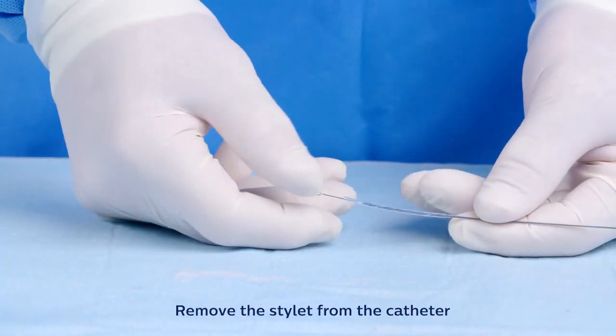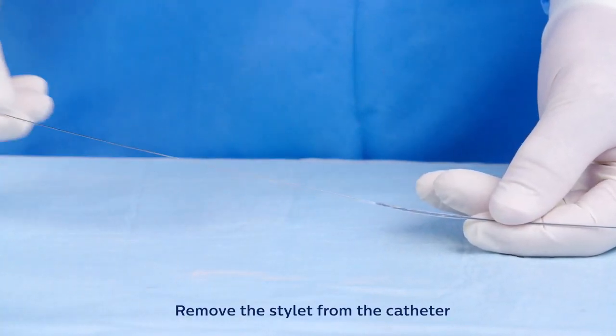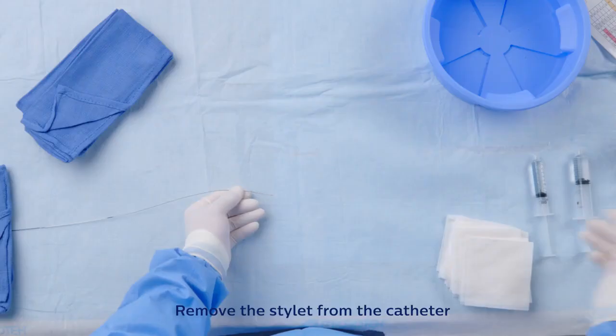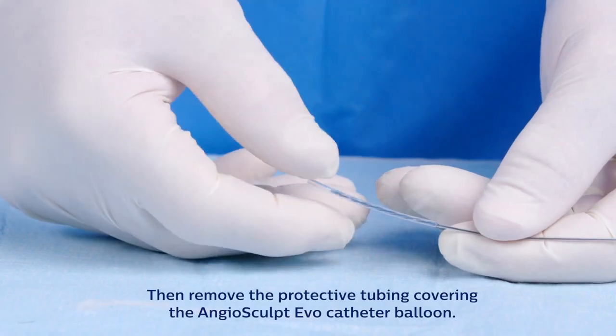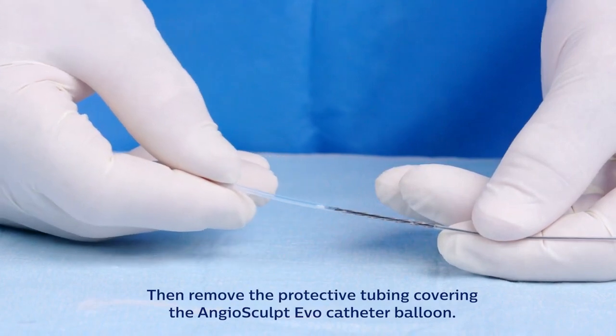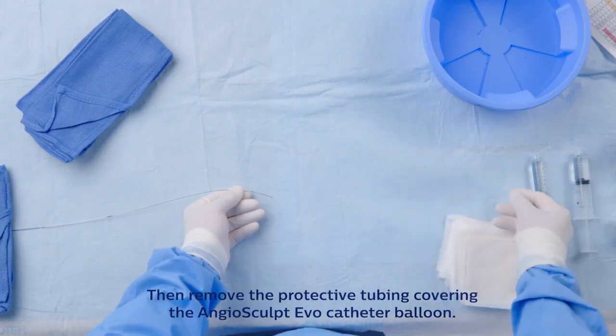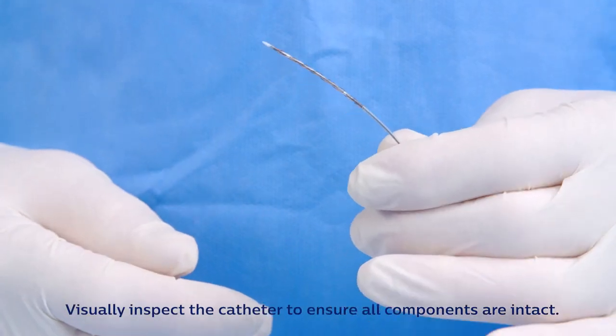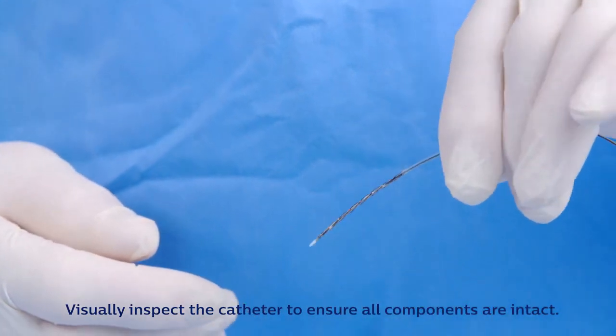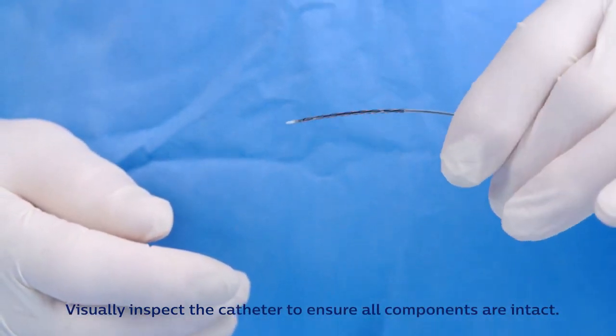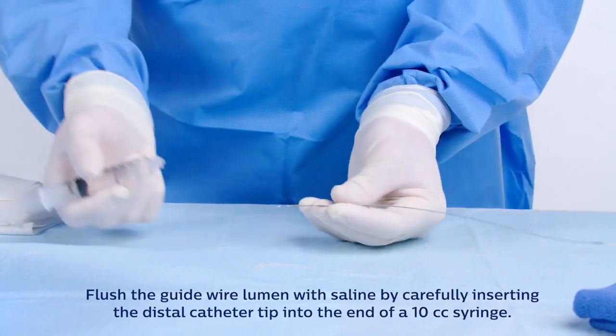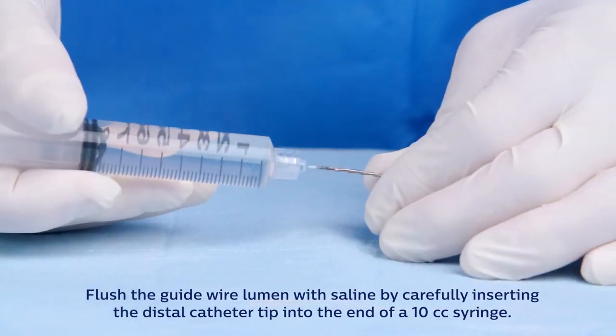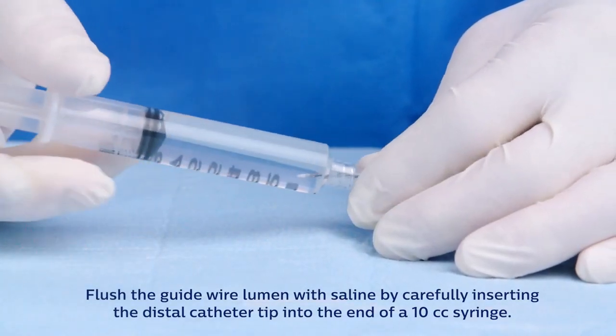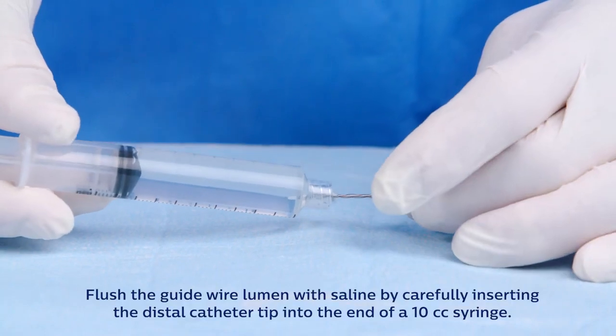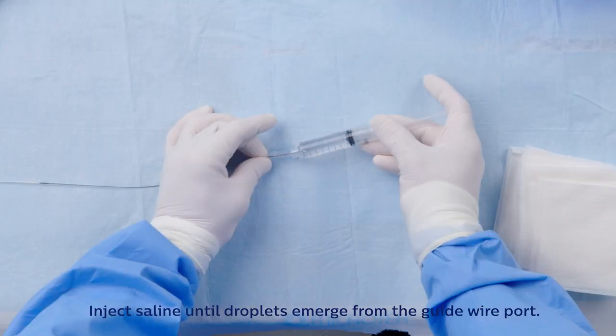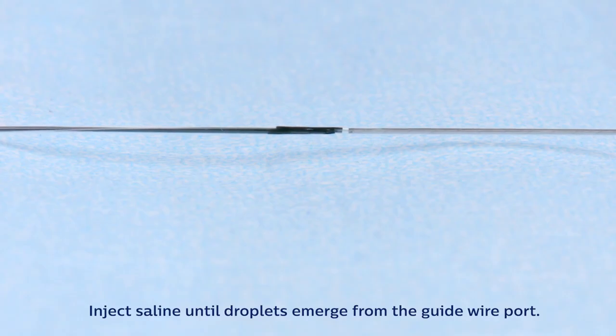Remove the stylet from the catheter. Then remove the protective tubing covering the AngioSculpt Evo catheter balloon. Visually inspect the catheter to ensure all components are intact. Flush the guide wire lumen with saline by carefully inserting the distal catheter tip into the end of a 10 cc syringe. Inject saline until droplets emerge from the guide wire port.